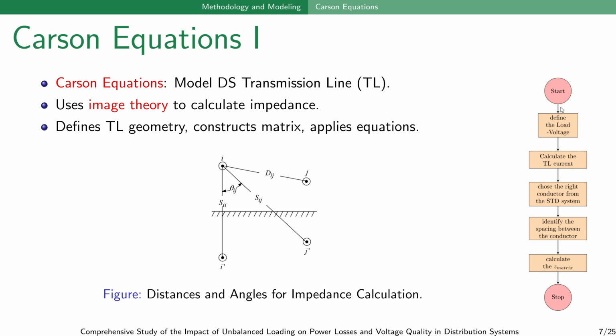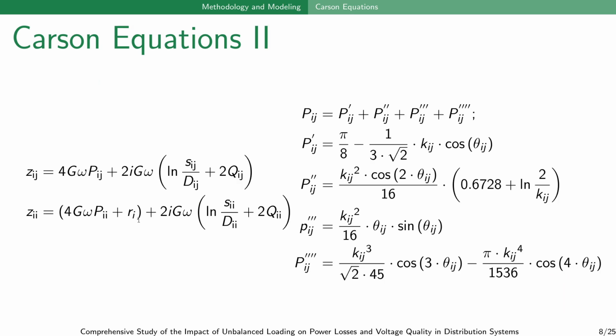And this is a small flow chart that helps us to effectively determine the impedance between the three phase and the earth. Started by defining the voltage level and then calculate the transmission line current, and then choose the conductor from the standard systems, and then identify the spacing between the conductor and then calculate the Z matrix. And Z matrix is calculated using this sample equation, in fact, that helps us to calculate the impedance matrix, and the other equations can be found in the paper.